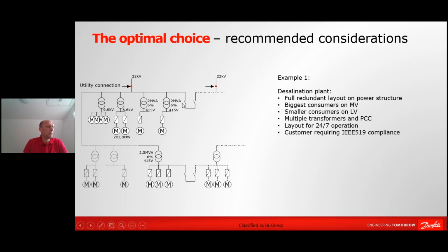that you can actually disconnect or connect your full supply from either the one feed or the other feed of power. Then you have a lot of drives up here on medium voltage level, 6.6 kilovolts, where you have both direct online motors and motors fed from drives. And you have maybe also some additional drives here fed from medium voltage down to 400 volts, fed and driven by frequency converters or VSDs.